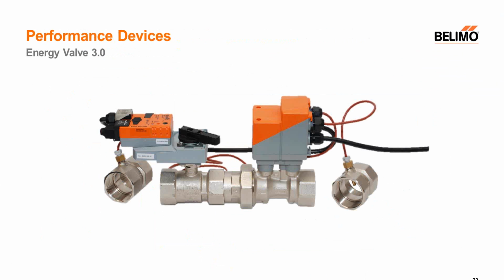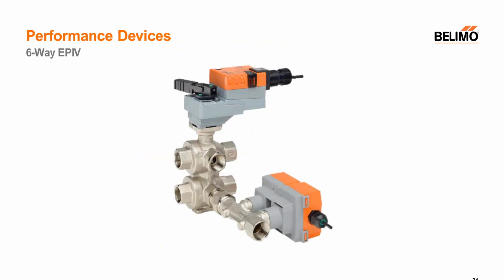The poster child we have for performance devices is our energy valve product. And it does all those things. It has smarts for the delta T management. It has a flow meter for flow control. It has the 2 temperature sensors. It is the best example of what a performance device does. Another product you may not be familiar with is our 6-way valve, but it's a 6-way EPIV, an electronic pressure independent valve. It's intended to allow both hydronic heating and cooling, so a 4-pipe system, to push cooling or heating water through a single coil. And instead of that just being position based, we can now allow that to be a pressure independent operation by measuring flow rate and modulating the valve to maintain the desired flow. So those are performance devices.